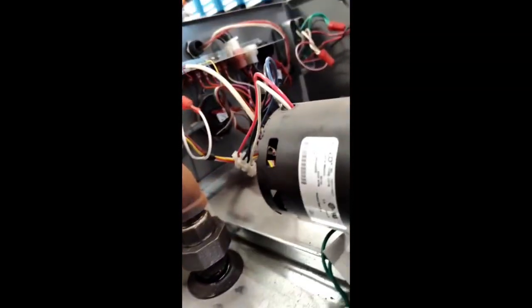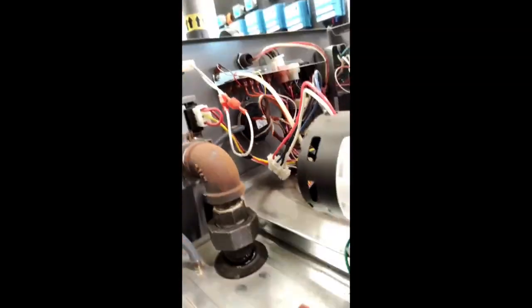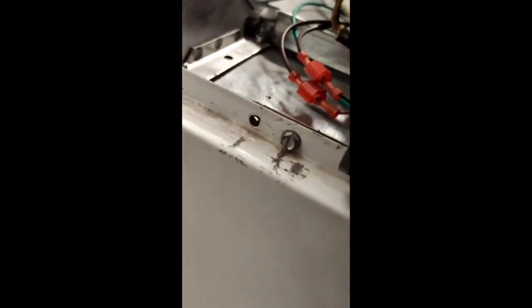But, you know, looking at this diagram, it's a very simple Lochinvar. And they're actually easy to PM as well. But this is the part that's confusing. It says water pressure switch, then you got air pressure switch, which that's that right there. That's the air pressure switch, which senses the induction motor, the pressure inside of the cabin where the heat exchangers are, so it knows it's getting airflow.